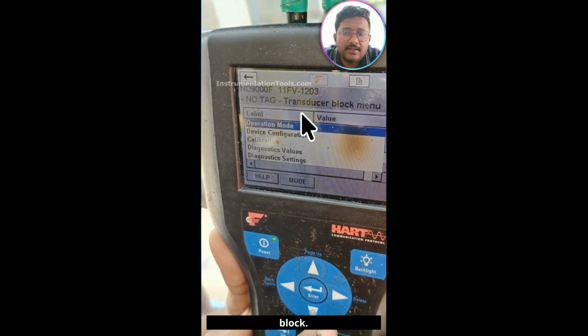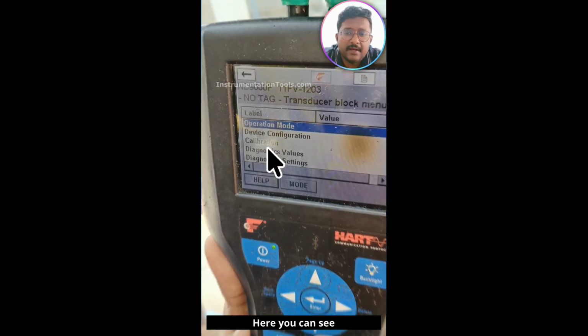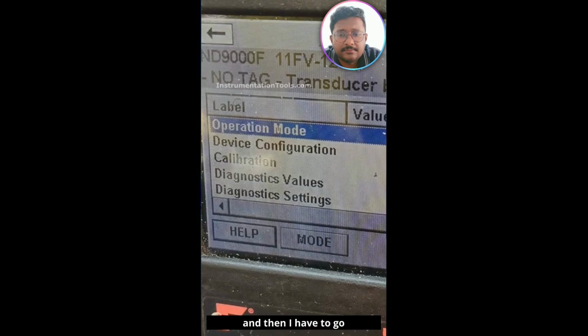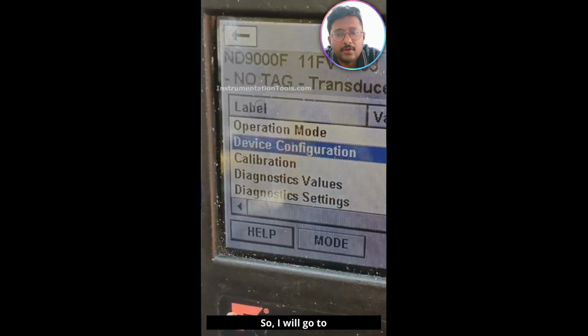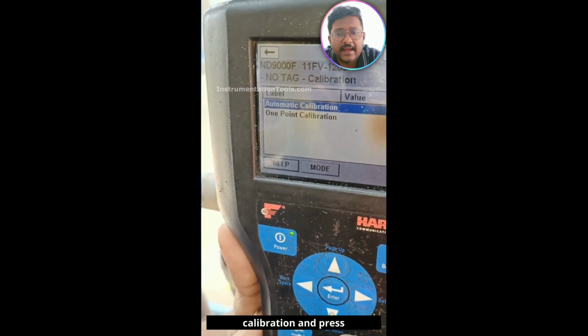See, this is a transducer block. Here you can see different menu items, and then I have to go to the calibration for doing the automatic calibration. So I will go to calibration and press enter. I am using the arrows here, up arrow, down arrow, left and right, so that for the navigation I can do it inside the communicator. Okay, and then I will go to the automatic calibration.